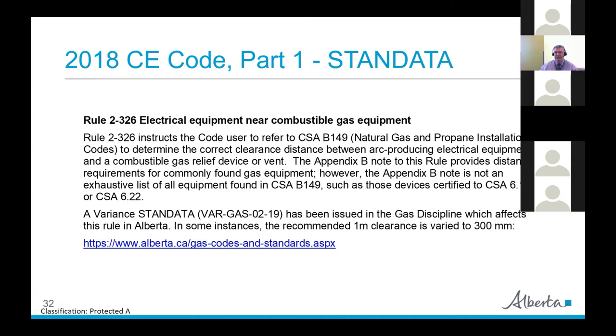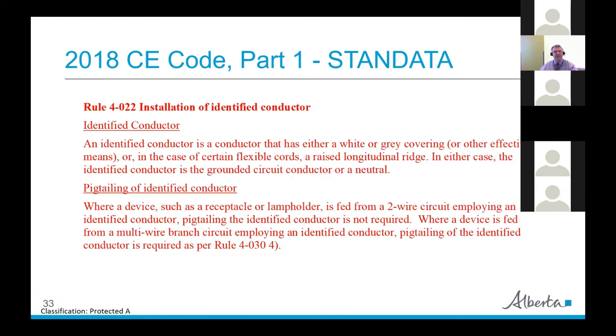Another stand data on Part 1 relates to installation of the identified conductor — specifically pigtailing of the neutral. If there's a two-wire circuit, pigtailing is not required, but if it's fed from a multi-wire branch circuit like a three-wire circuit, pigtailing is required as per rule 4-0304.